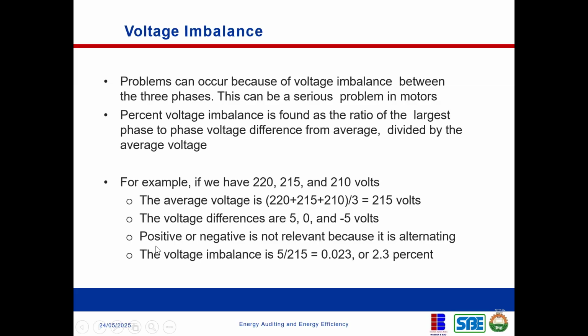As already explained, whether positive or negative is irrelevant because it's alternating current. The voltage imbalance is therefore the highest difference among the three phases — so the highest here is 5. If it were minus 10, that would be the highest instead, since the sign doesn't matter. So we divide 5 by the average voltage, 215, giving 0.023, which is a 2.3% voltage imbalance.